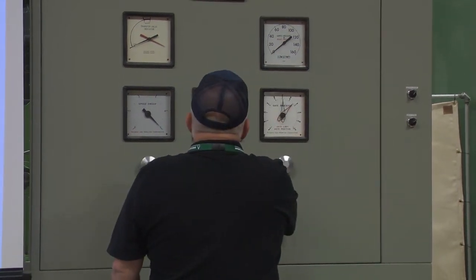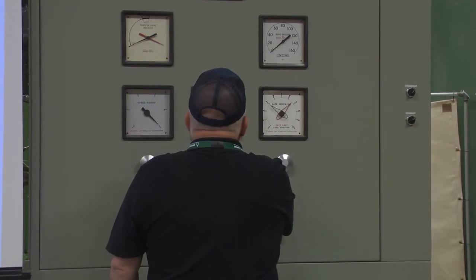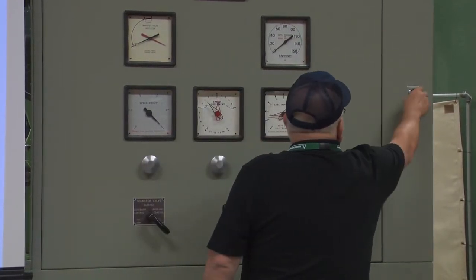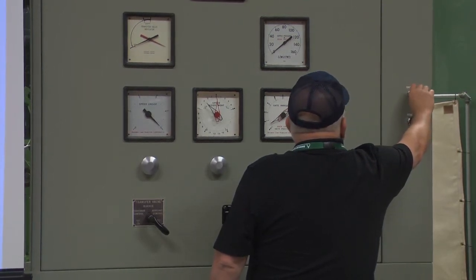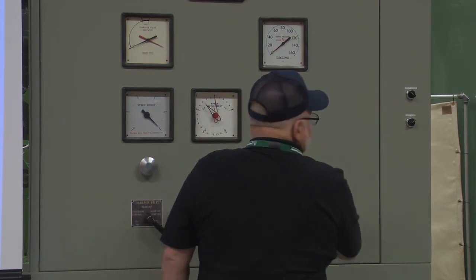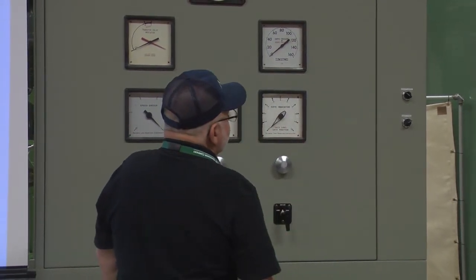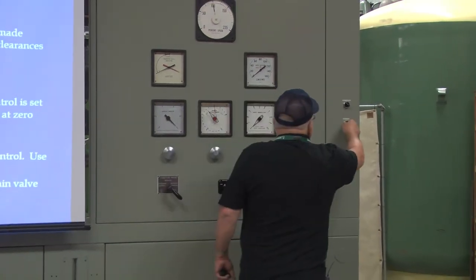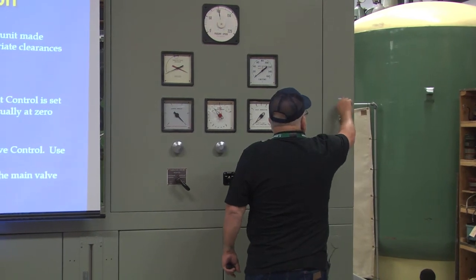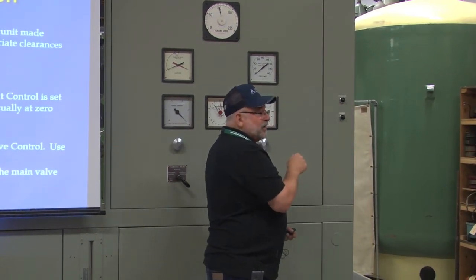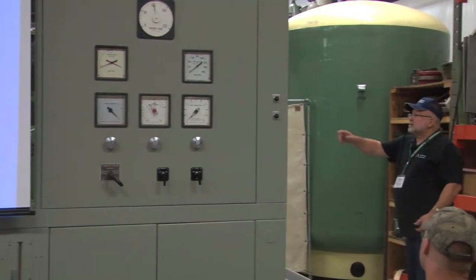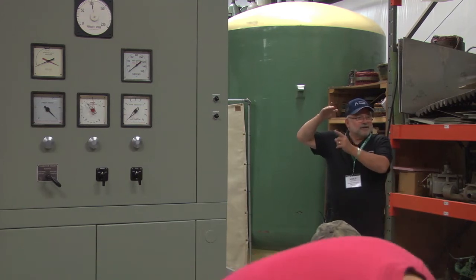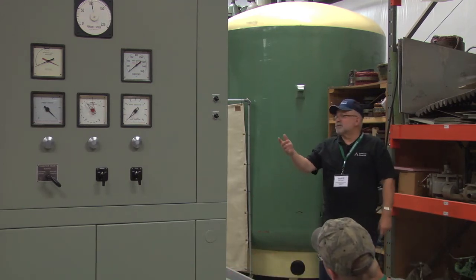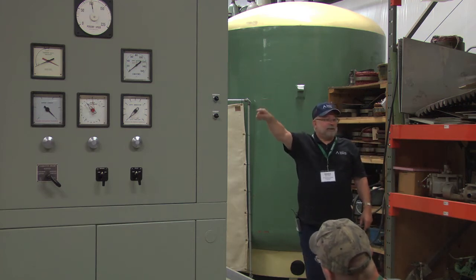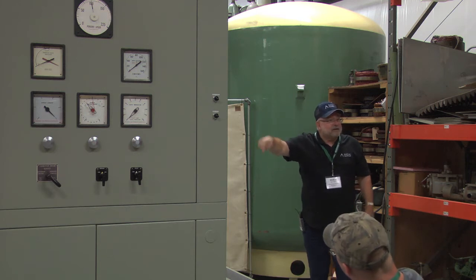So you're going to make it where nothing will move, okay? And the shutdown solenoid, now we will block up the shutdown solenoid. We'll cheat here. You'll have to do it like you would normally do it. It's got a little block on it there. You just raise it up, all right? And if you happen to have the partial shutdown solenoid above that, which comes down to the top side of the T handle, this one doesn't have one, but you guys probably have that, okay?